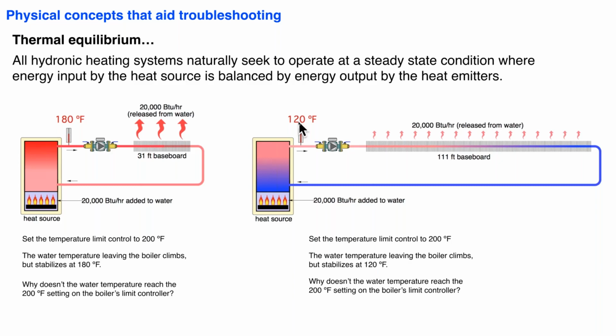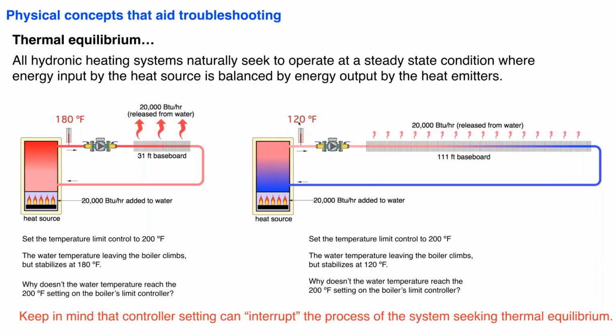It's always trying to find that balance. And the other thing to keep in mind is that controllers can interrupt the process of that system seeking thermal equilibrium. For example, if we put the temperature controller on this system and we set it at 160, the system would keep heating up, the temperature would rise, and once we get up to 160, that limit control would click off. The process was on its way towards 180 degrees, but the controller intervened. It shut off the system before thermal equilibrium could be achieved.